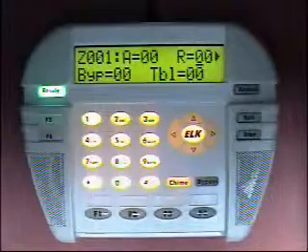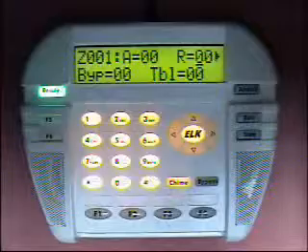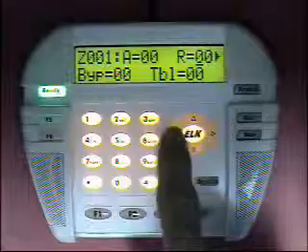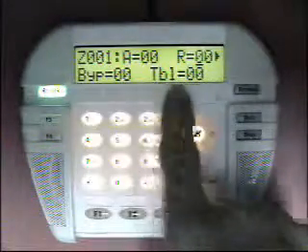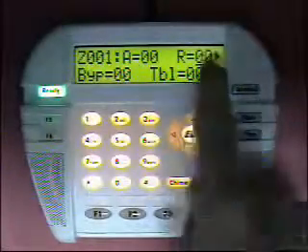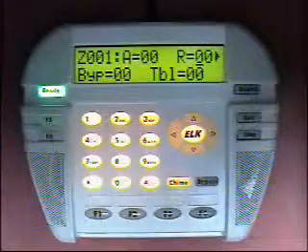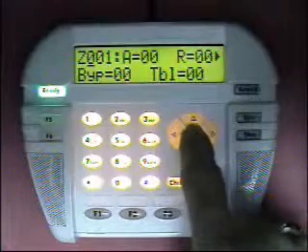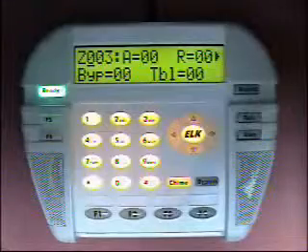If you want to remove a reporting code, make sure you enter 00. All the reporting codes in all these menus are programmed exactly the same, so we will not cover this programming again during this session. The alarm, restoral, bypass, and trouble codes — if you do not want to transmit any of these, put a 0 in those locations and they will not be transmitted.